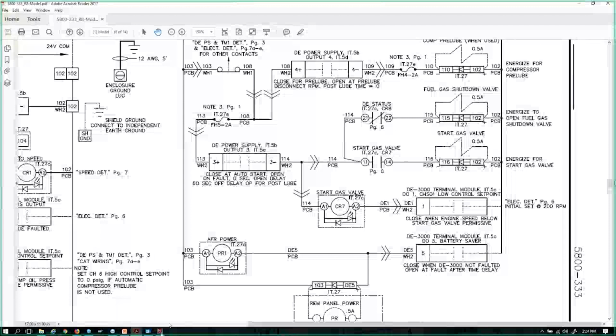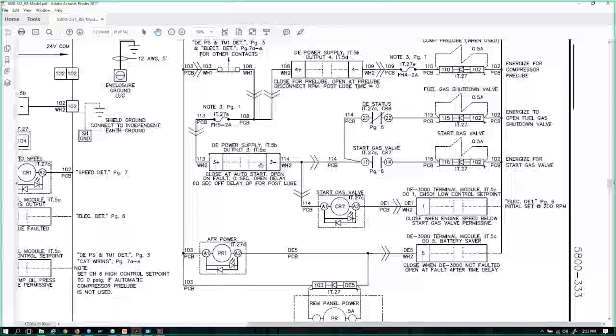So what we are saying, if we look back at the software, if I'm below 500 RPM, close this or turn this output on. And what that's doing for us is that's allowing voltage here with a ground here, that's allowing this relay to energize, and this contact goes closed, and we have power now to energize a start gas valve. And again, I mentioned earlier that there's a lot of people that use start gas safety valves on the edge of their skid. It doesn't actually control the start, but what they're trying to do is turn the start gas valve off if they don't need it. So if they're up and running, they don't need start gas valve pressure.